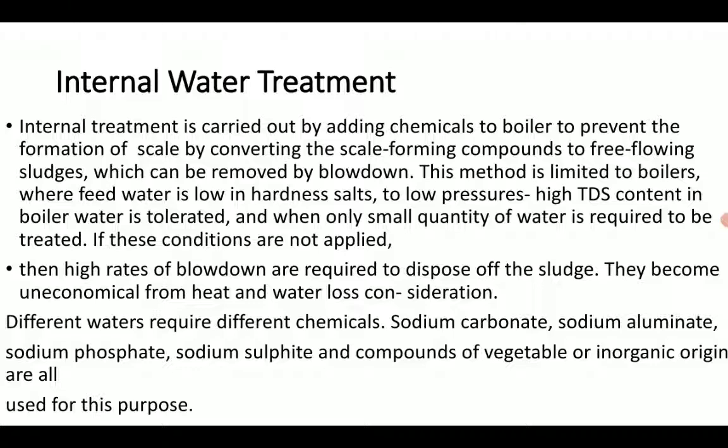This method is limited to boilers where feed water is low in hardness salts, to low pressure and high TDS. TDS means total dissolved solids. So this we call TDS. A higher content of total dissolved solids in the boiler water is tolerated, and only a small quantity of water is required to be treated.